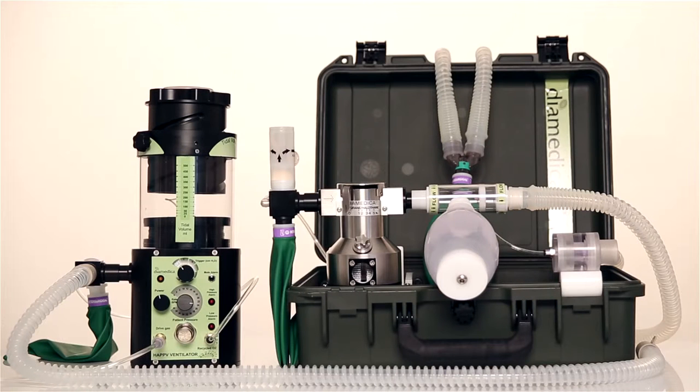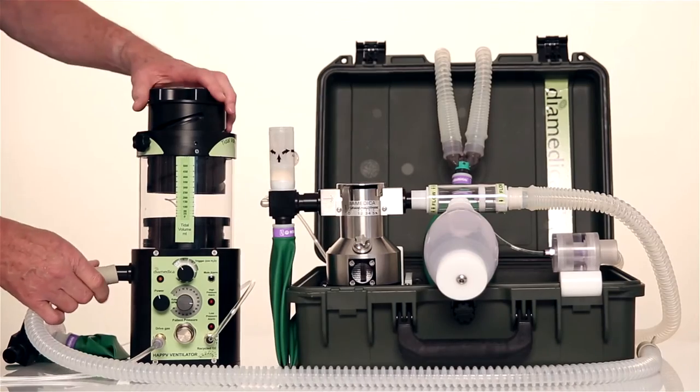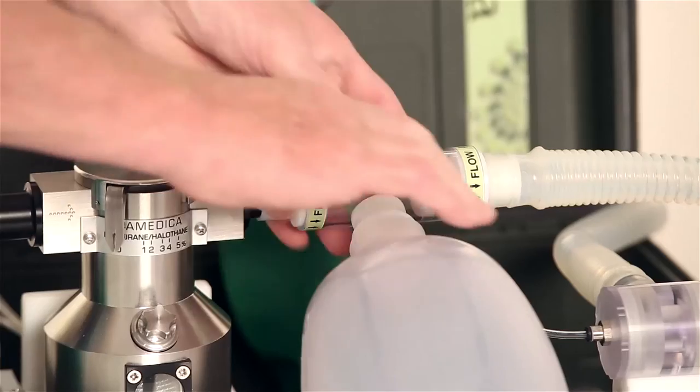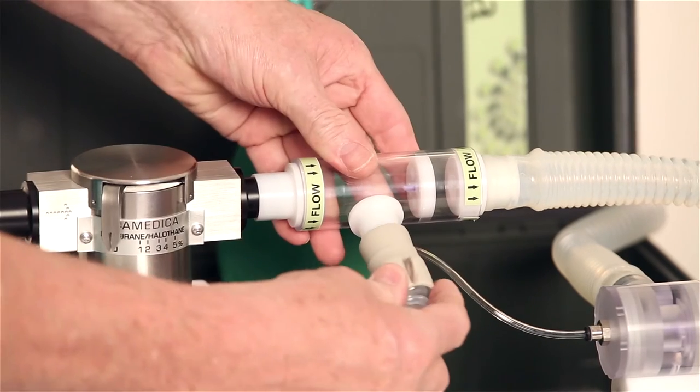If the Helix is used with the DPA-02 anesthetic machine, then the circuit block is removed and the ventilator outlet is simply connected to the DPA-inspiratory valve in place of the self-inflating bag.